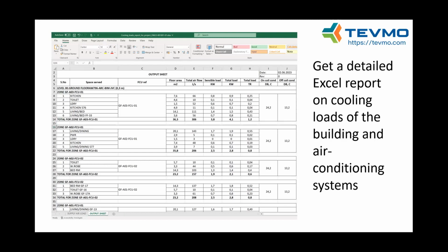And as you for sure know, there are many different methods in ASHRAE textbooks for calculating cooling loads. So the most known are probably RTS, radiant time series, the one that we use. And another one, transfer function method, is also very known, and heat balance method is also very known. So there are a few of them, the most used ones, and I'll discuss it a little later. The one that we use, the one that other software uses, yes, and I'll discuss it later.